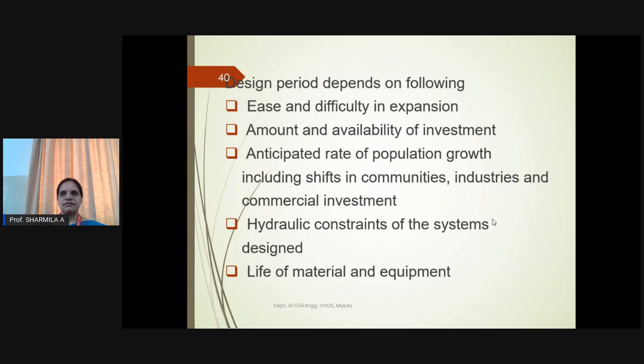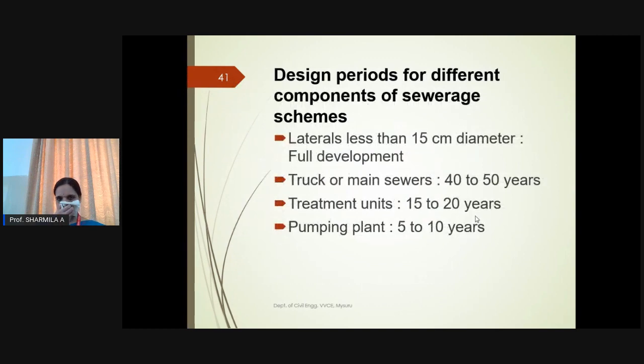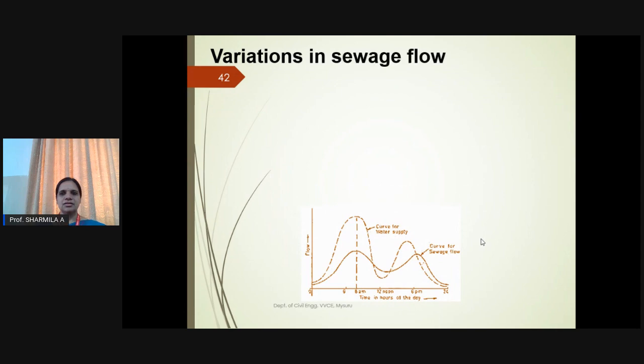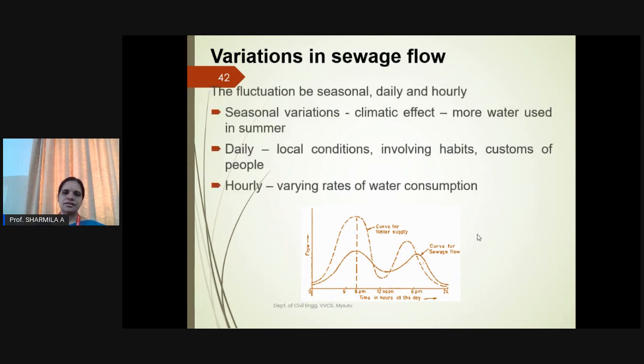For future periods, provision has to be made in the design capacity of various components — known as design periods. Design periods vary depending on the activity: ease and difficulty of expansion, amount and availability of investment, anticipated rate of population growth, hydraulic constraints of the sewer system, and life of material and equipment. Design period for different components: laterals less than 15 cm diameter — full development; trunk or main sewers — 40 to 50 years; treatment units — 15 to 20 years; pumping plant — 5 to 10 years.